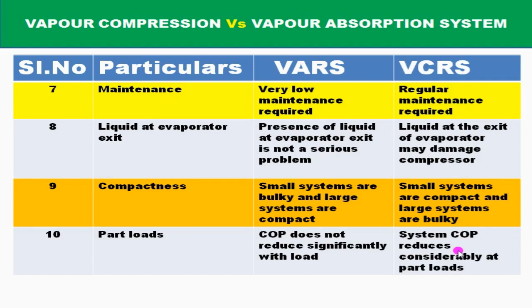Evaporator superheat is not very important in case of vapor absorption refrigeration system because the performance of the vapor absorption system is not affected by the evaporator superheat. However, in vapor compression refrigeration system, the performance of this system depends on the evaporator superheat. Hence, these systems are sensitive to the evaporator superheat.